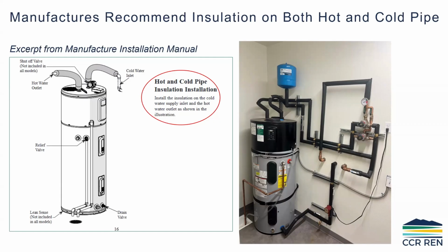On retrofits, you can put a tiny recirculating pump with a crossover from the hot water to the cold water at the farthest fixture in the house, and a demand switch at that farthest fixture, or in the hallway near it.